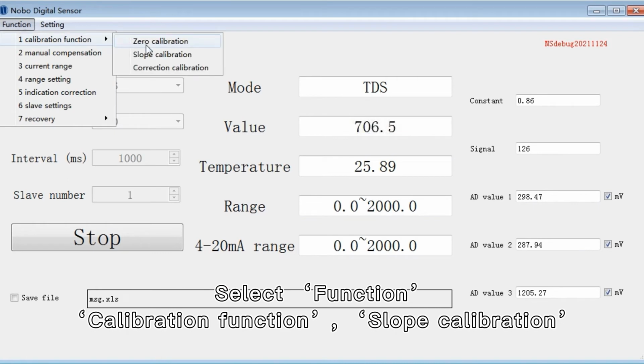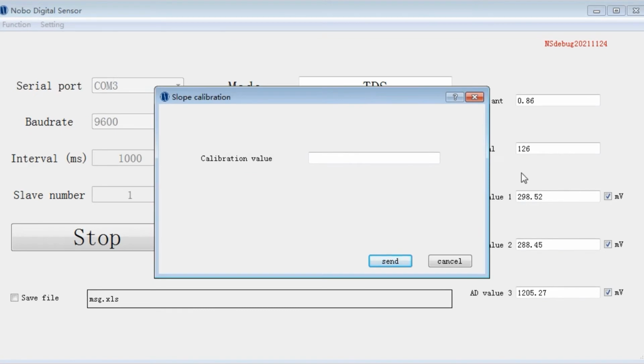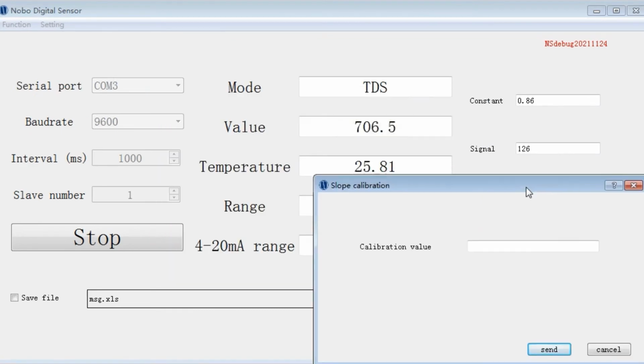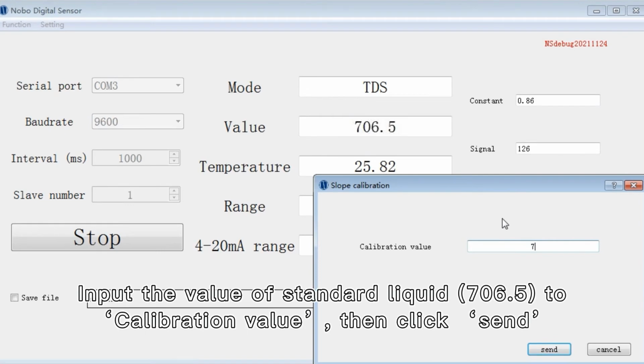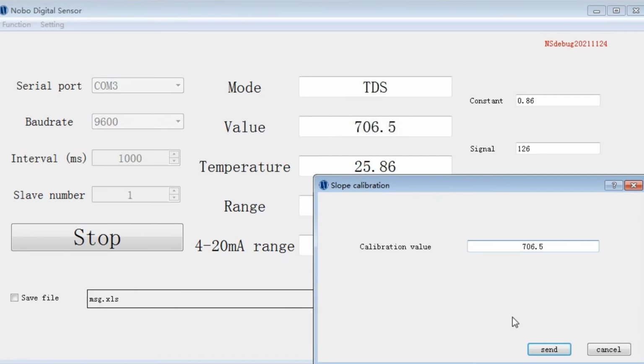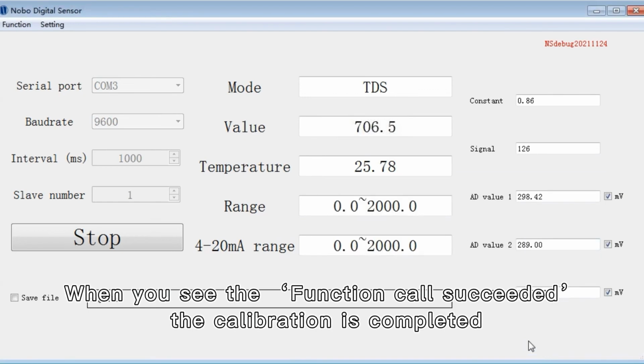Select function, calibration function, slope calibration. Input the value of standard liquid, 706.5, to calibration value, then click Send. When you see the function call succeeded, the calibration is completed.